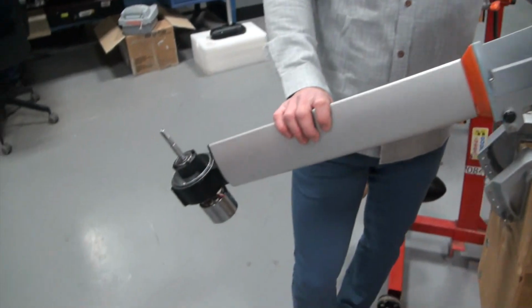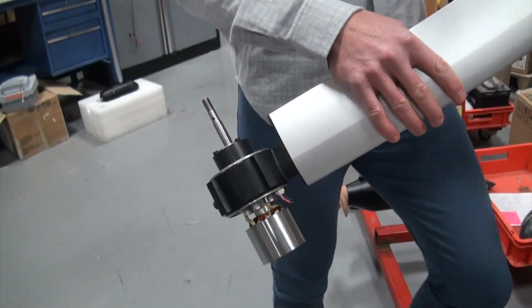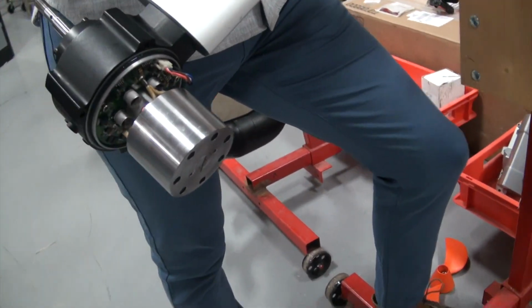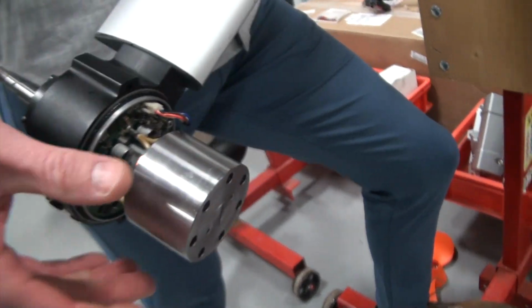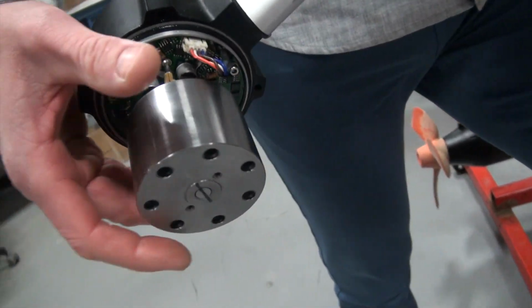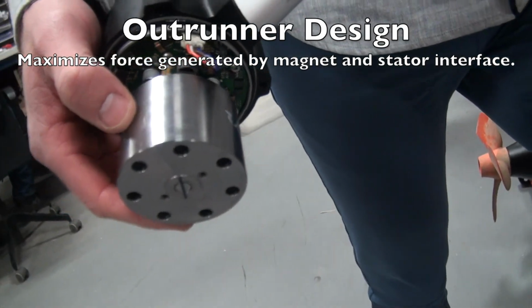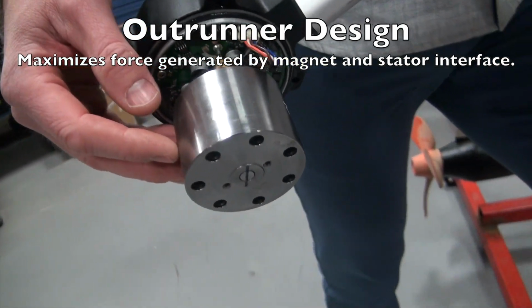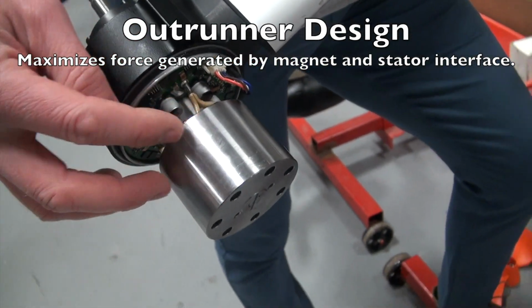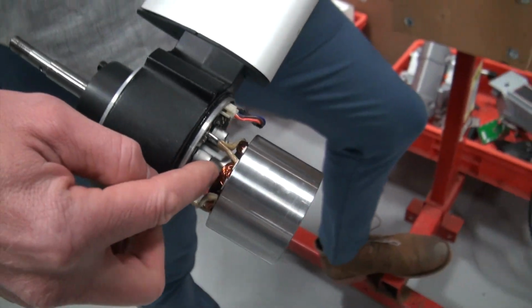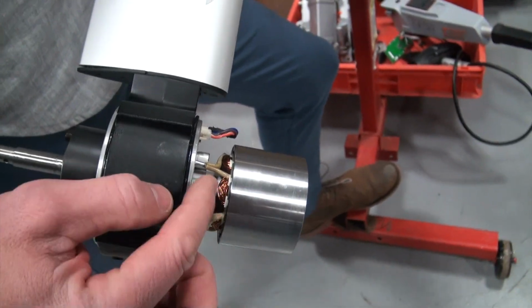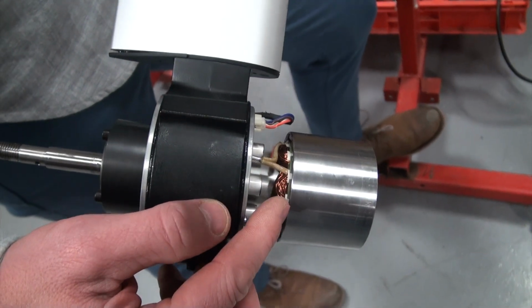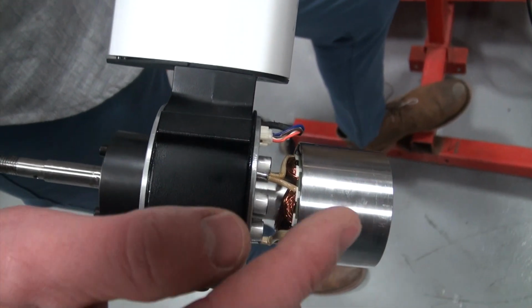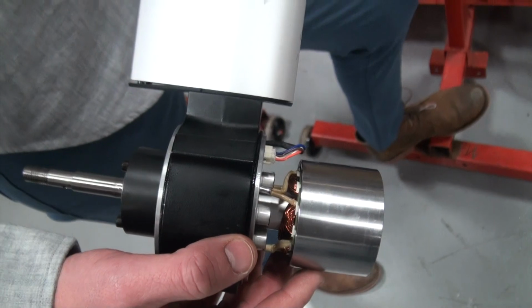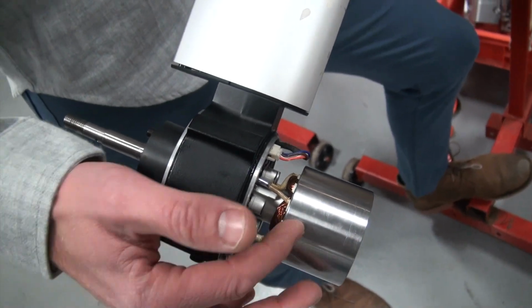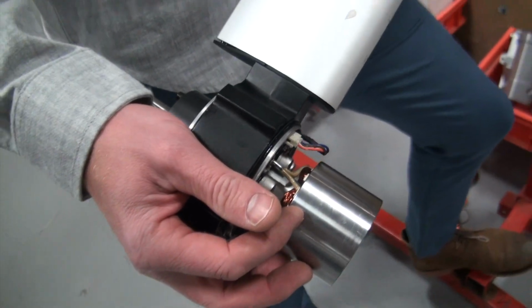So what do we have here? Looking closely at the motor, we can see the main components of this electric unit. In the front is the motor bell. This is an Outrunner design, meaning the motor bell with the magnets rotates around the stator, which is stationary in the center with the coils. The benefit is that the forces between the magnetic fields are further from the center of rotation, giving a longer arm for force and therefore creating more torque.